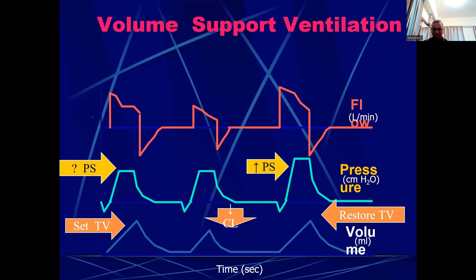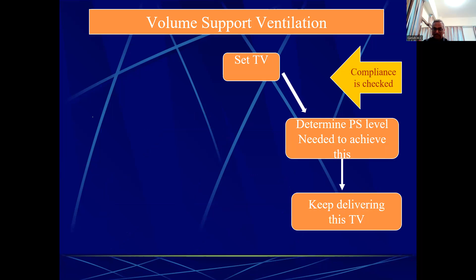So this is volume support ventilation in a nutshell. Set tidal volume. The machine checks the compliance with 3 test breaths. It determines the pressure support level needed to achieve this, and then it keeps delivering this tidal volume. If compliance changes, it increases the pressure support level needed to achieve that tidal volume. So it is a closed loop ventilation.